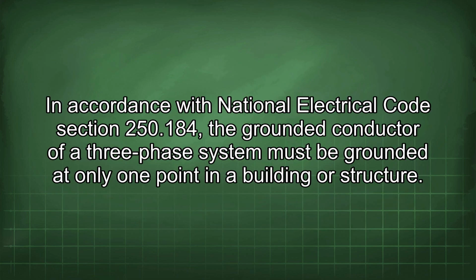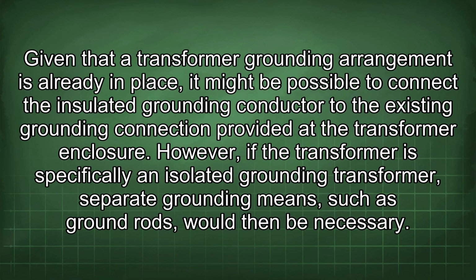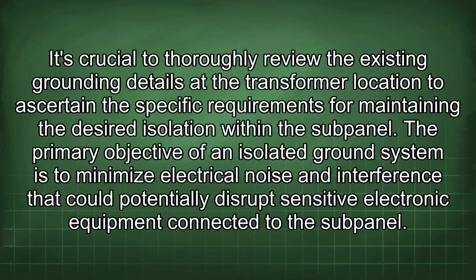In accordance with National Electrical Code Section 250.184, the grounded conductor of a three-phase system must be grounded at only one point in a building or structure. Given that a transformer grounding arrangement is already in place, it might be possible to connect the insulated grounding conductor to the existing grounding connection provided at the transformer enclosure. However, if the transformer is specifically an isolated grounding transformer, separate grounding means, such as ground rods, would then be necessary. It's crucial to thoroughly review the existing grounding details at the transformer location to ascertain the specific requirements for maintaining the desired isolation within the subpanel.